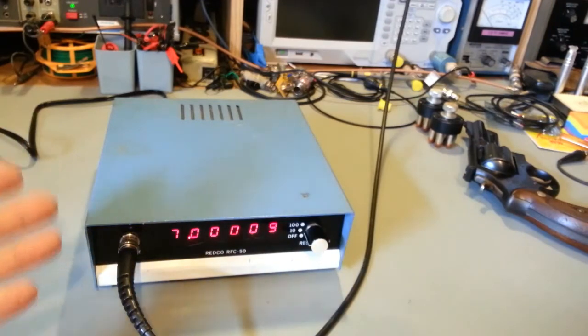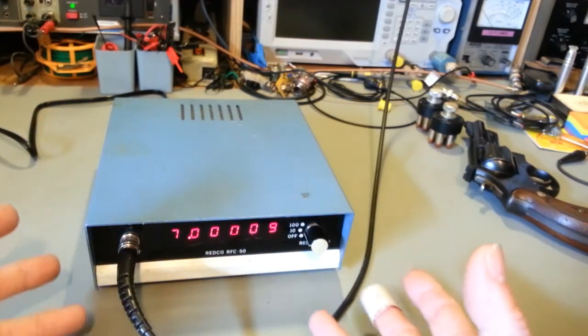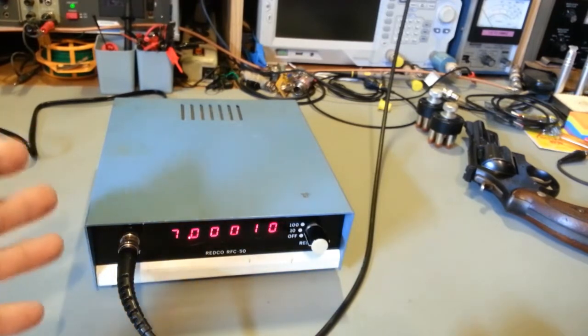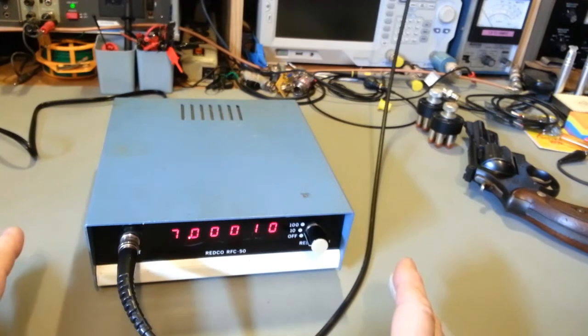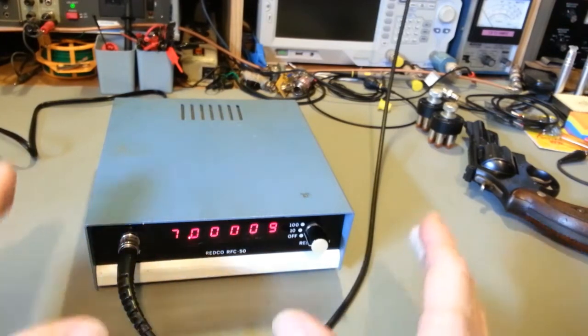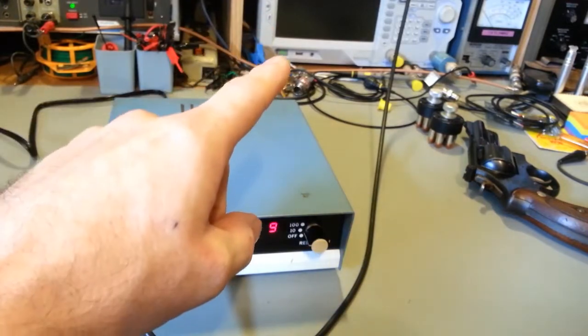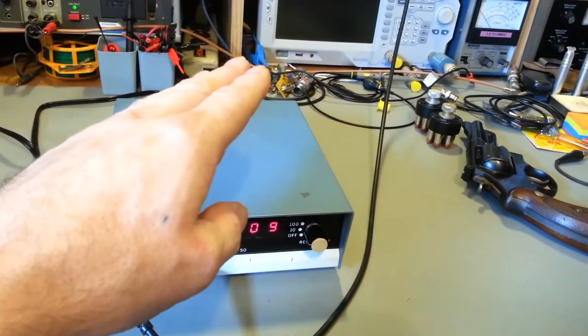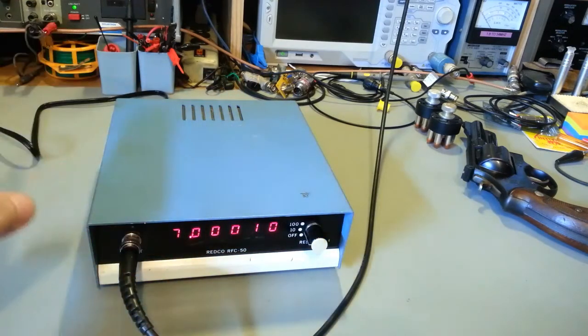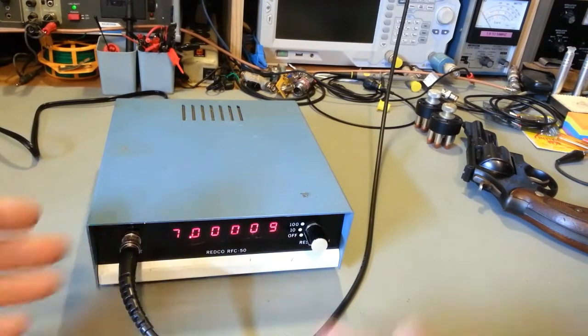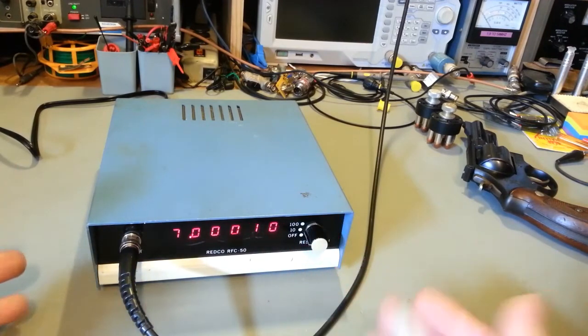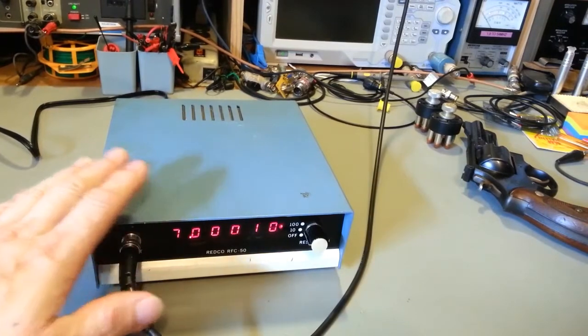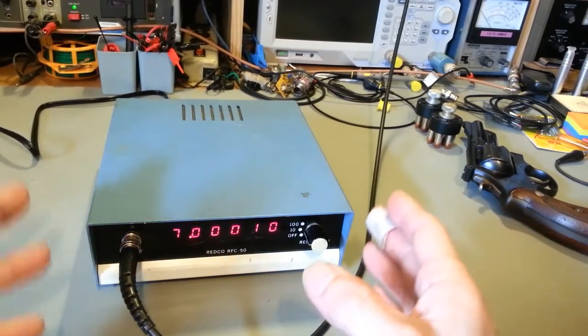Like I said, it's not a precision instrument. It does not have an oven control, well actually it is almost oven control, that's kind of the problem with these. You need to let these things warm up and the temperature stabilize. That's the whole point of this video. Let it warm up. Even test equipment, you're supposed to let that stuff turned on. Most labs will let something turned on for a day for it to stabilize in temperature. It's only got 10 and 100 Hertz resolution. This isn't high precision, but you want to let something like this turned on for about an hour. The reason is it's old.